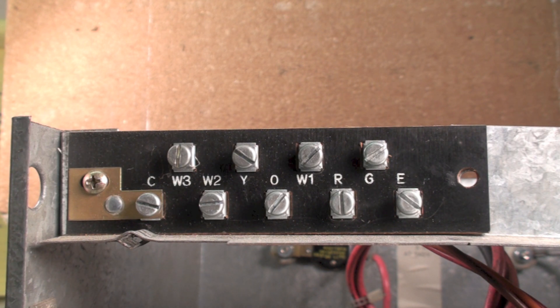I hope that makes sense. I haven't gone over heat pumps yet, and there's a ton of stuff to go over on heat pumps and how they work and how the different ones are set up. But that's just a quick overview on where you'd put your meter probes to find out if you actually had 24-volt power to the backup heat. Hope this helps.